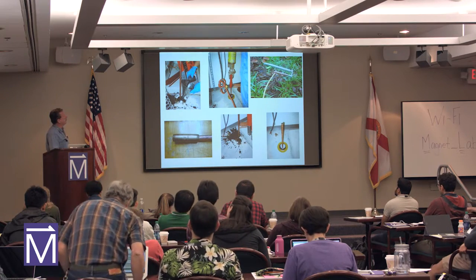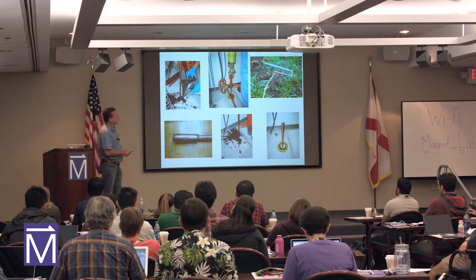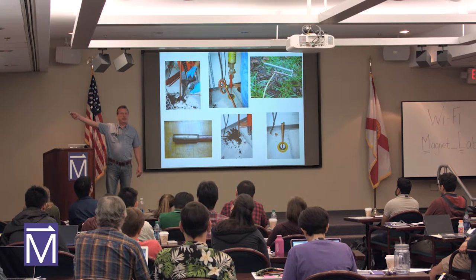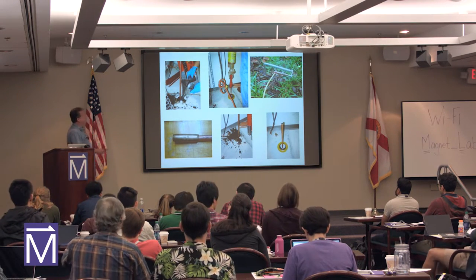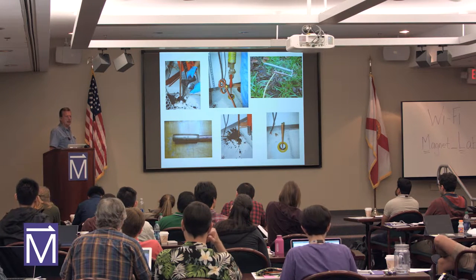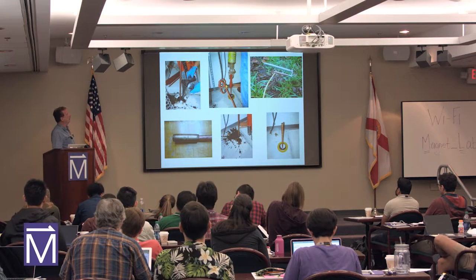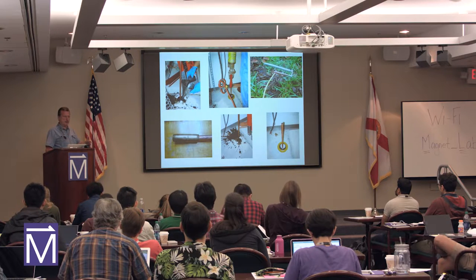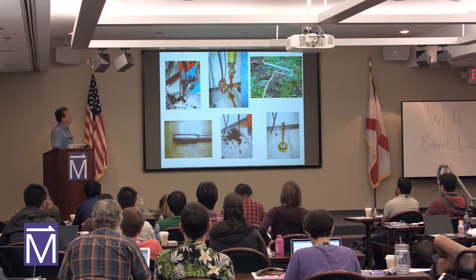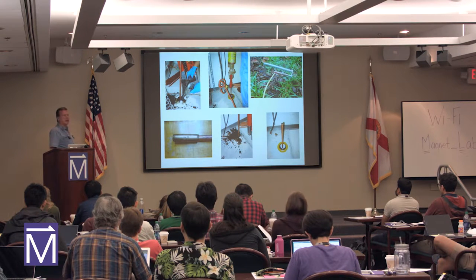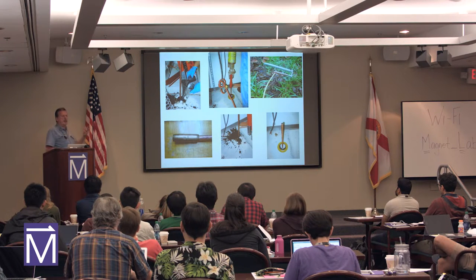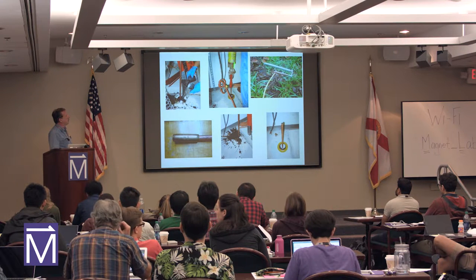There are two methods. This is actually an electrode which was put over the street. And we put DC into the ground. Then there is another electrode, say, to measure voltage outside. And then we put yet another electrode to our grounding rod under investigation. This way we measure, it is like a three-probe measurement. We measure how the resistance of this rod changes.